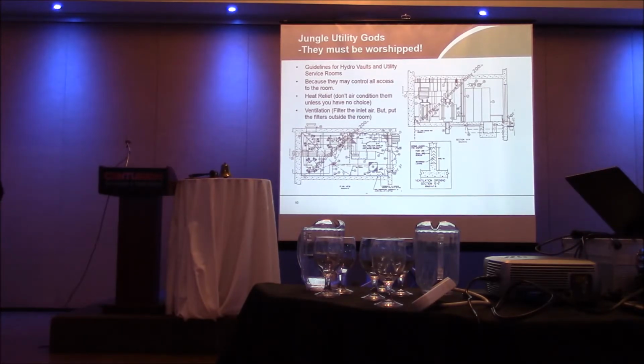So if the filter clogs and it restricts the flow of air to the room, and the room overheats because you've got 20 kilowatts of heat going inside that room with the 1,000 kVA transformer, it isn't going to be long before the high temperature alarm in the room's going to go off, and then the utility's going to show up, and they're going to shut you down until you fix the problem. And when I say shut you down, I mean turn you off, shut you down.